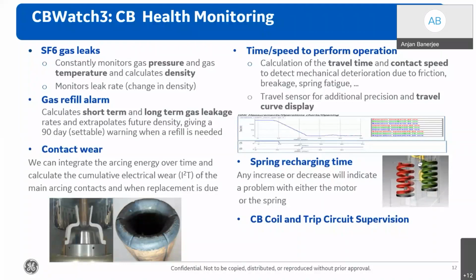CB Watch, as I said, monitors each and every critical component of the circuit breaker, starting with gas leakage. The device captures pressure and temperature from the sensor fitted in the circuit breaker, and from pressure and temperature, the device computes density, and any change in density would be construed as a leakage from the circuit breaker compartment. Not only that, the device can predict what the density of the circuit breaker SF6 gas could be, for example, 90 days down the line.